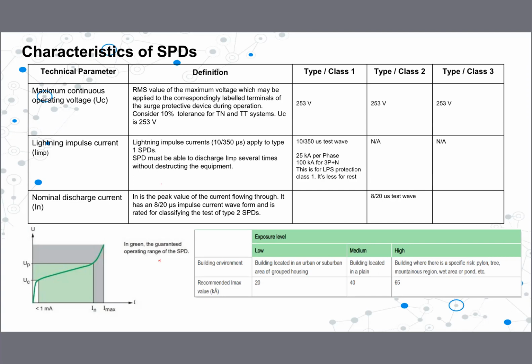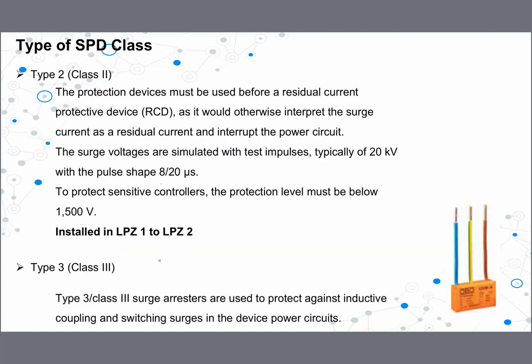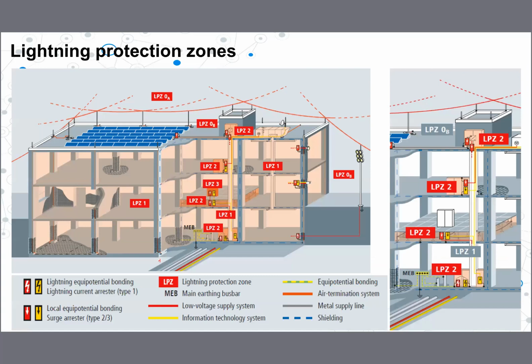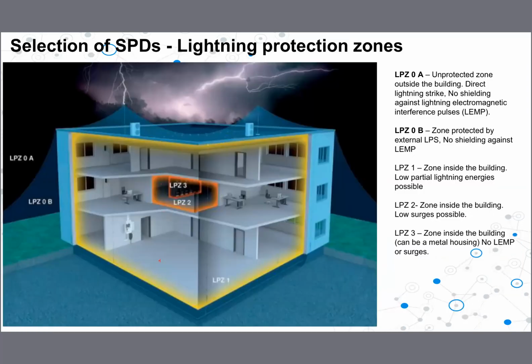If we don't have a lightning protection system, then definitely we need type 1 surge protectors everywhere. We need to evaluate it, actually. But if there is no lightning protection system in the building, then everywhere will be like zone 0A, so everywhere we have to install type 1.